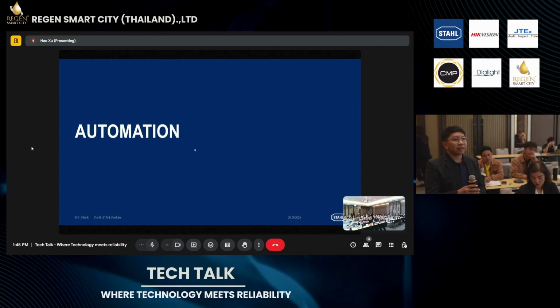Again, I get the question. I refer to the standard. If you refer to IEC standard 60079 part 17, part 17 is a standard required for inspection and maintenance of equipment. The standard recommend the periodic inspection. Yep. As I shared with you, basically, lifetime is at least 100,000 operating hours. 100,000 operating hours means normally actually around, if you calculate 8,000 operating hours a year, then this would come up to normally 12 operating years.